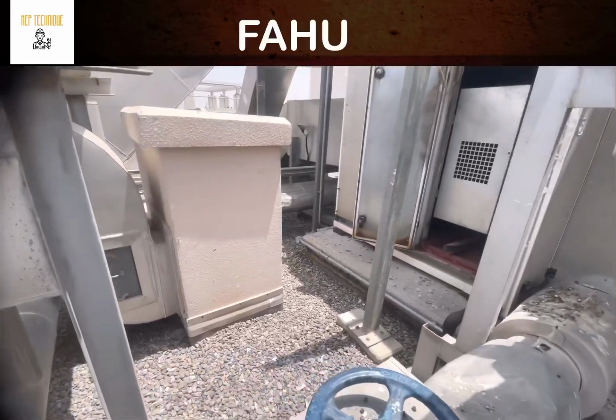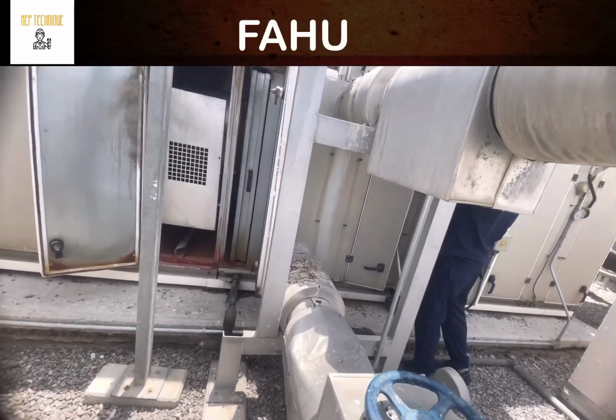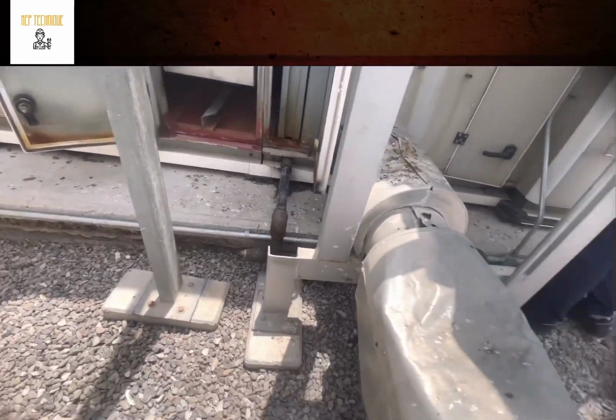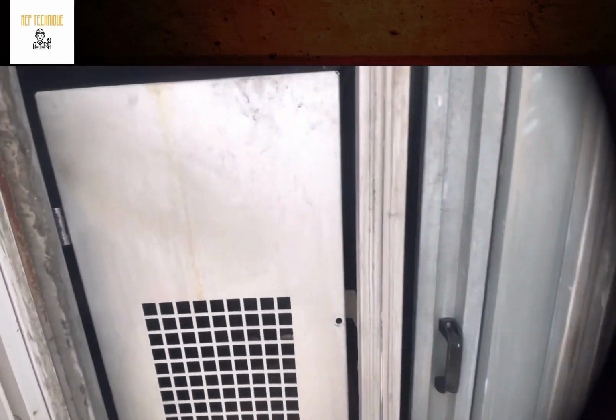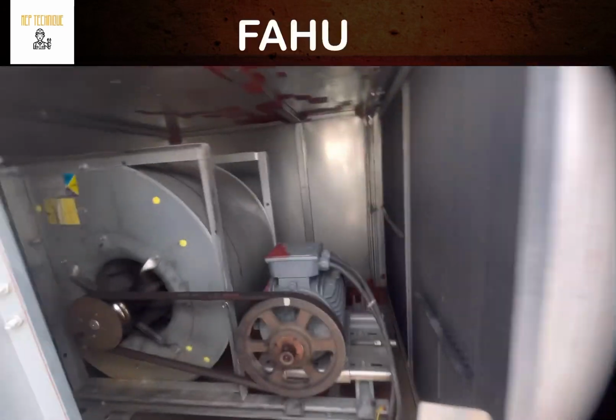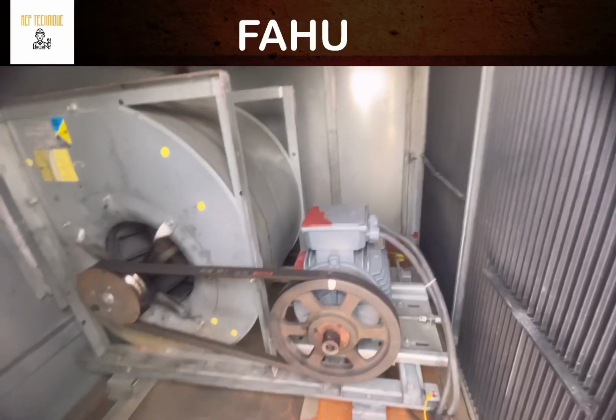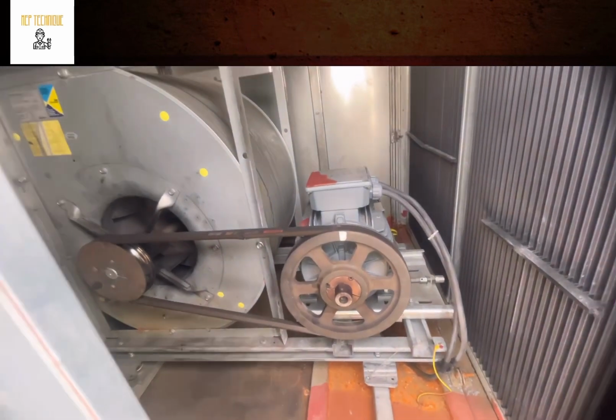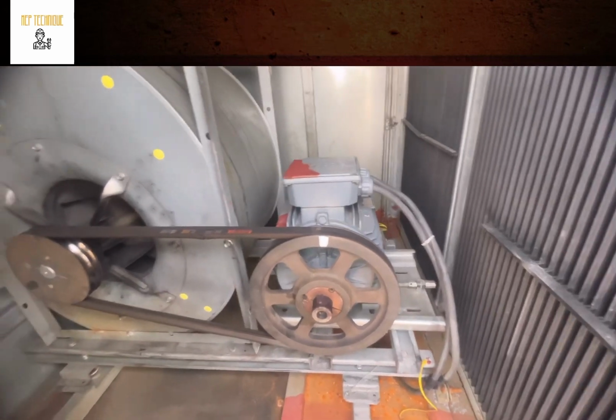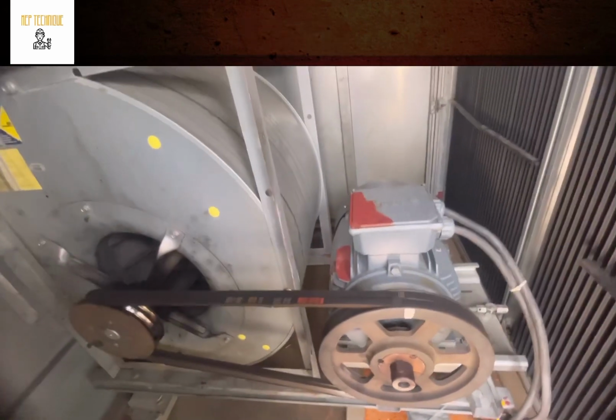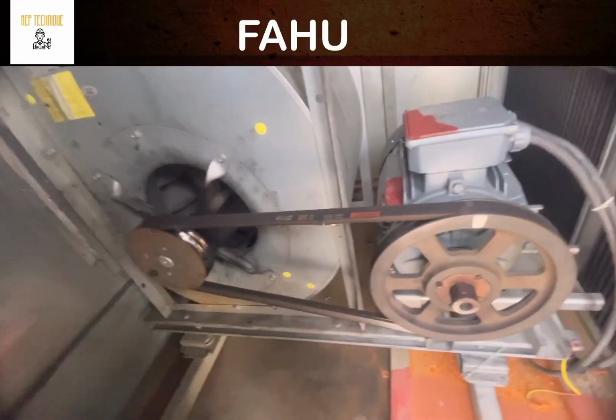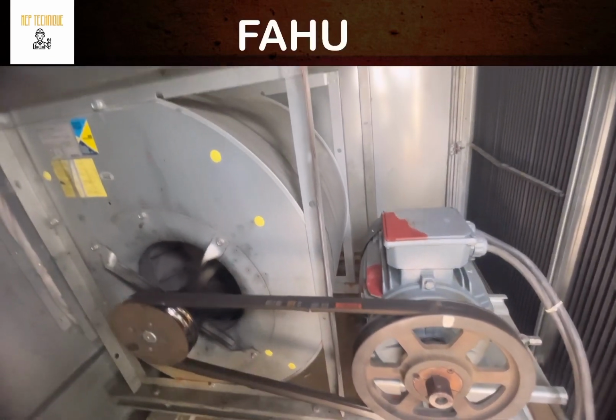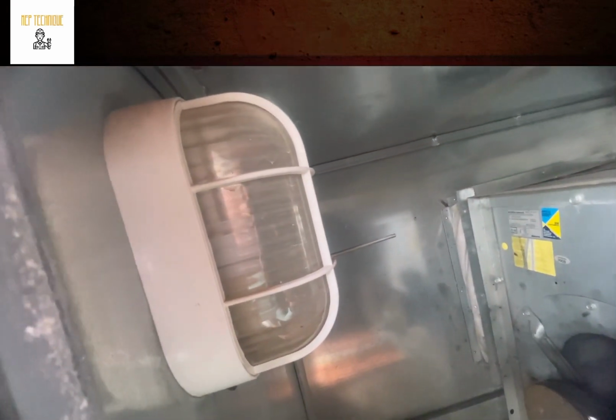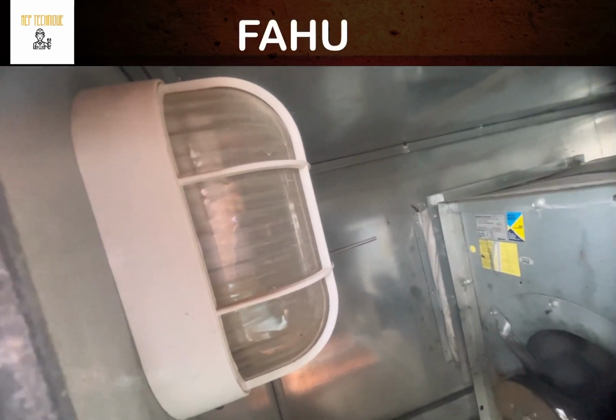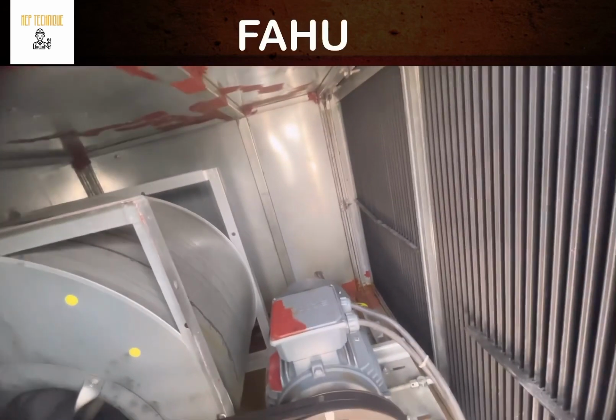After that we'll move to the motor and blower section. This is the most important section of the FAHU. Okay, you can see here, this is our motor and blower section. This is a belt driven blower. This is the motor, a three phase induction motor, which is operating the blower. And there is a light. If you open the FAHU, it will automatically turn on during maintenance. You need proper light to do the job.